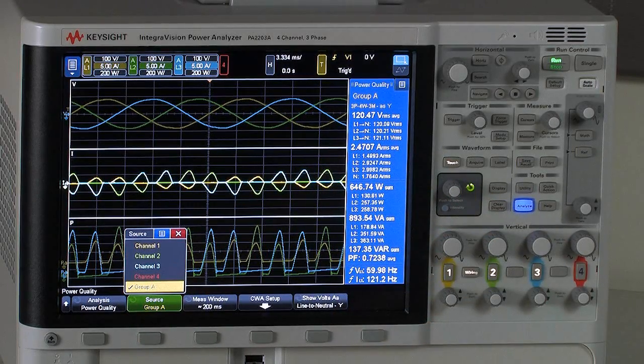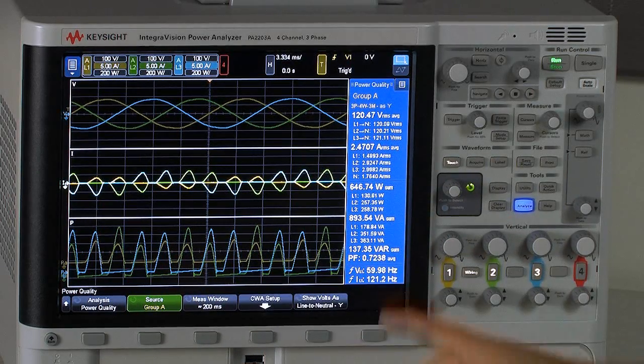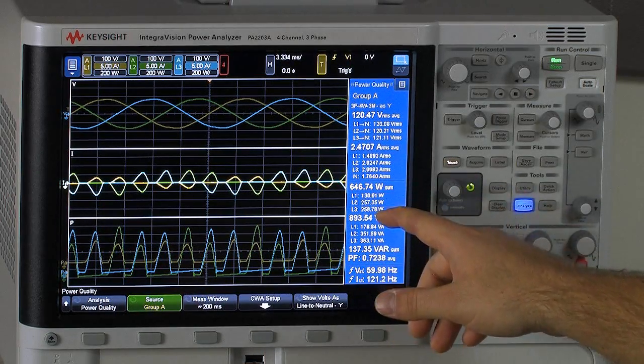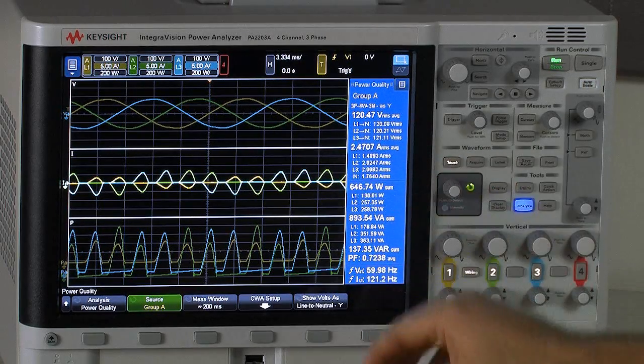And I see over here, my power quality panel, I've got a new set of measurements reflecting that group. So I can see the individual voltage and current measurements of each phase. And I can also see average measurements for the group.